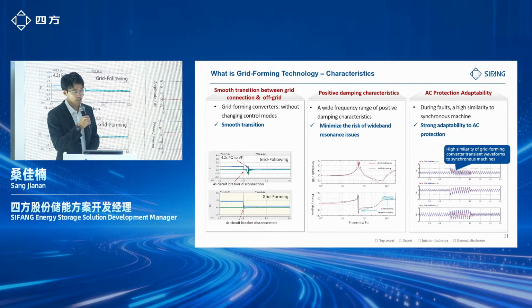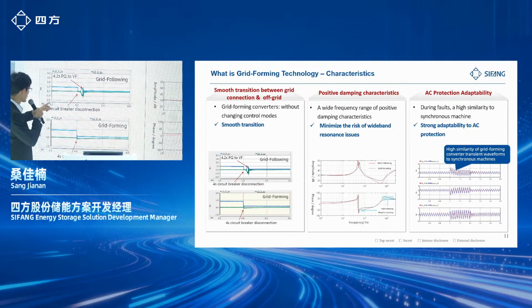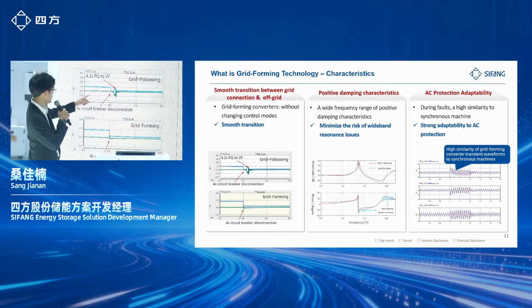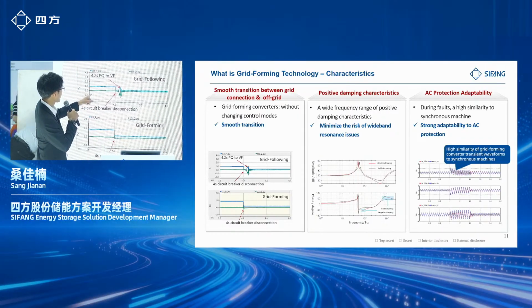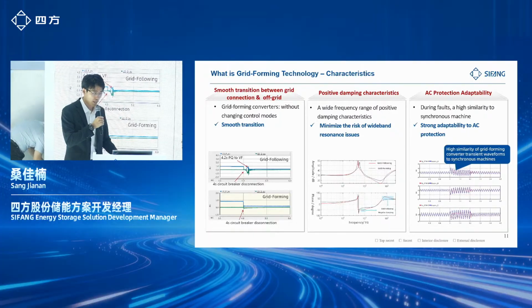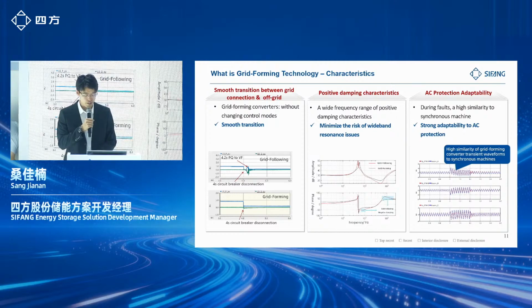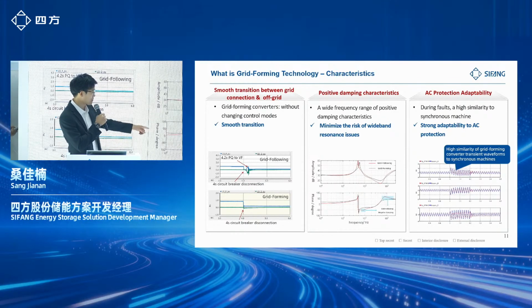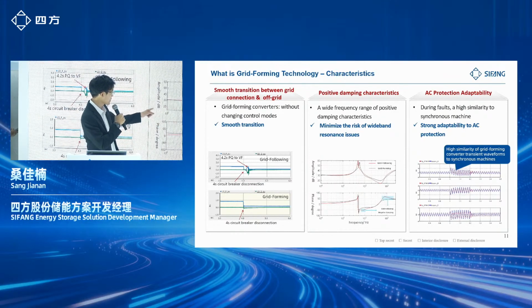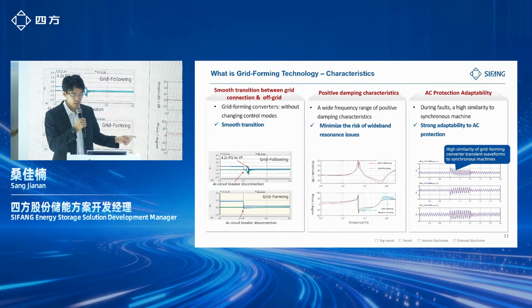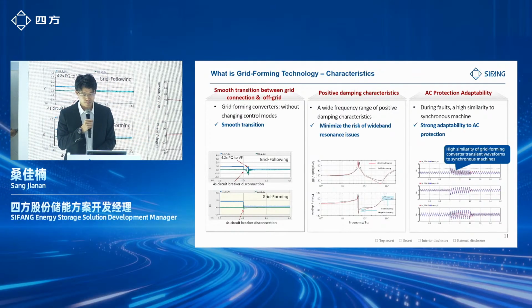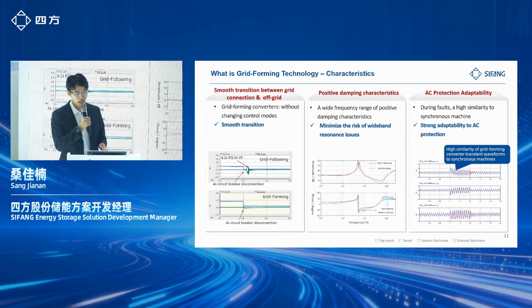And here is a smooth transition between grid connection and off-grid. The traditional solution makes some fluctuation during the transition from grid connected to off-grid, but there is no problem for the grid-forming solution. It also minimizes the risk of wideband resonance issues. From this Bode plot, you can see the phase curve always performs like positive damping characteristics. And the last one is AC protection adaptability, which means it performs with high similarity to synchronous machines.